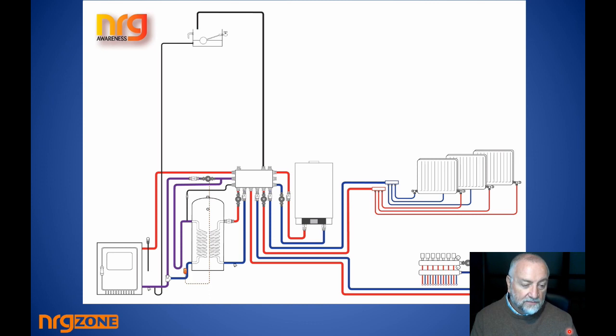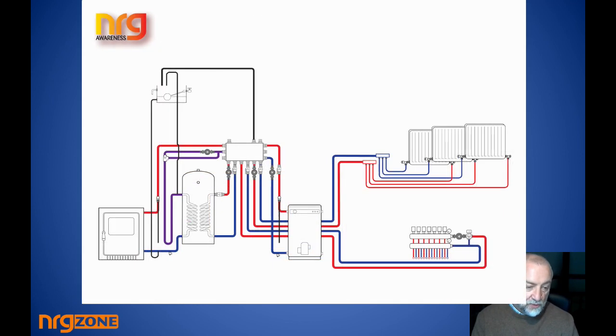I'll just show with the mixing valve on the underfloor here, and it'll be drawing water across. If the mixing valve needs to open the port to allow heat to be drawn from the unit, there's no pump at the unit. If you look for underfloor heating, the pump is at the manifold only, with this particular type of manifold I'm saying. And at the same time, if it is up to temperature and there's sufficient heat to be circulated in the floor, now this pump has no conflict. It can circulate within the mixing valve bypass circuit and pass around out to the floor. So you've got a very rapid heat up time, a very fast underfloor situation.